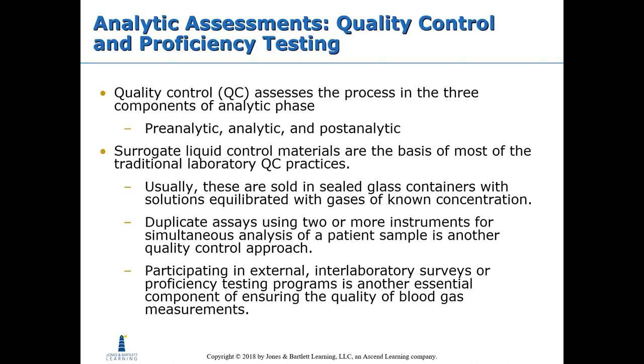Quality control assesses the process across three components of the analytical phase: pre-analytic, analytic, and post-analytic. Surrogate liquid control materials are the basis of most traditional laboratory QC practices — usually, these are sold in sealed glass containers with solutions equilibrated with gases of known concentration. Duplicate assays using two or more instruments for simultaneous analysis of patient samples is another QC approach. Participating in external inter-laboratory surveys or proficiency testing programs is another essential component of ensuring the quality of blood gas instruments.